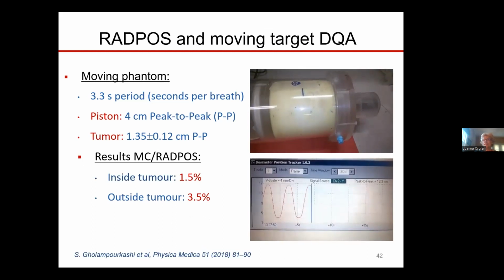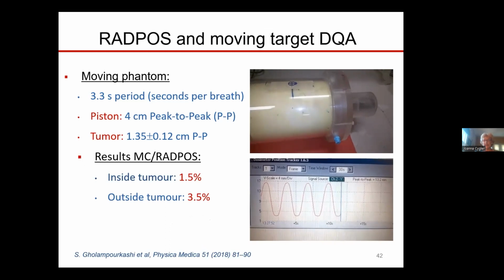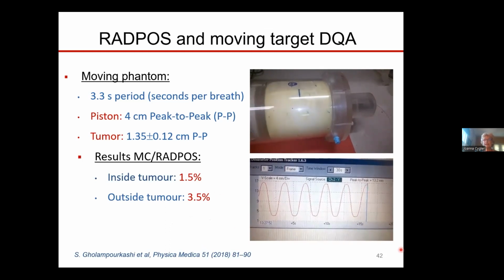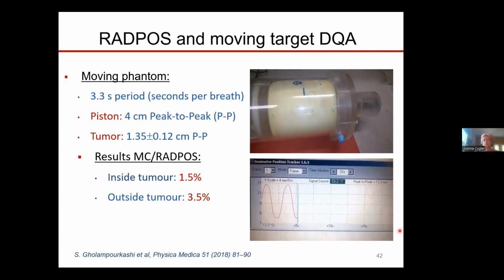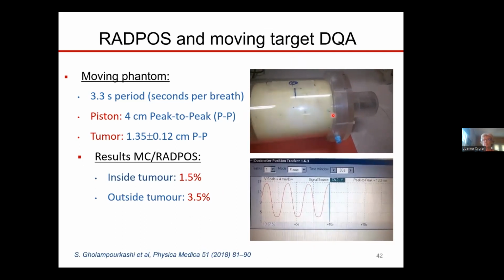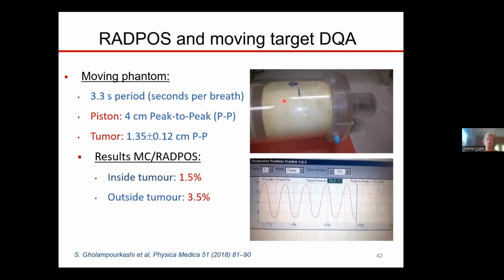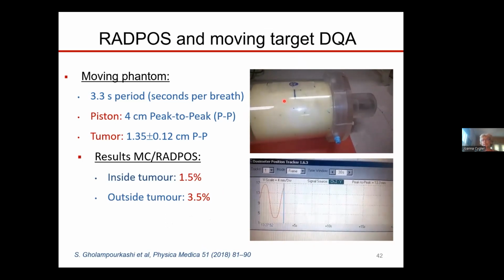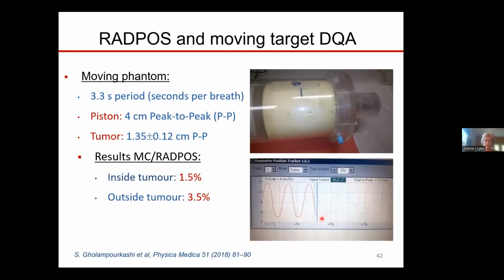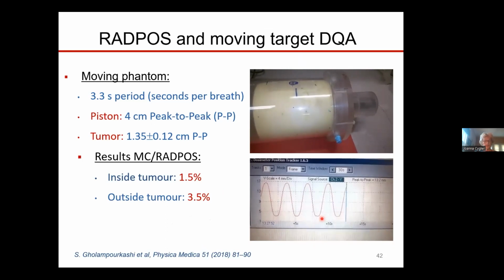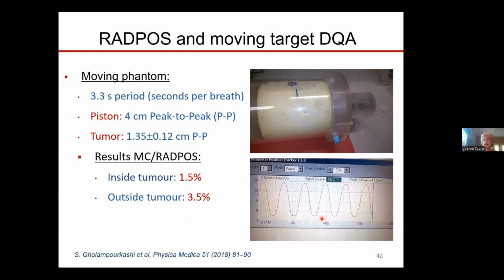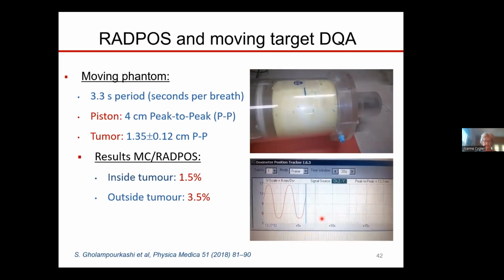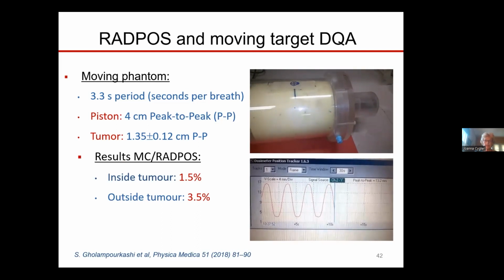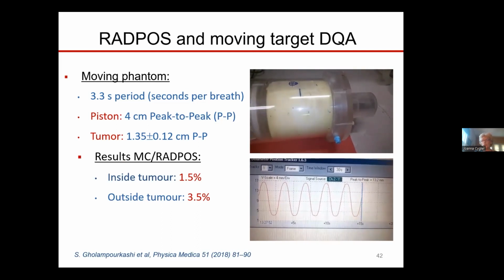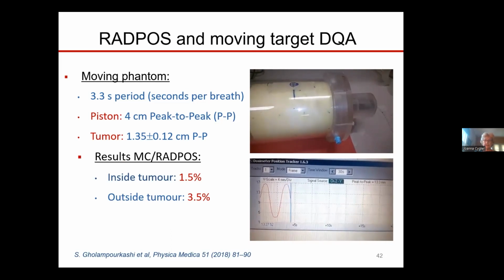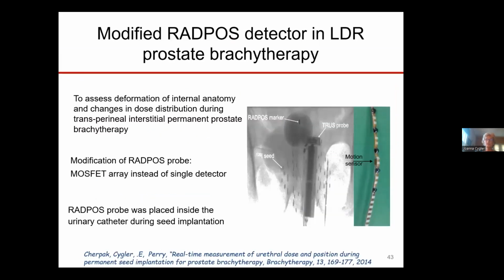This slide illustrates how the RADPOS can do these real-time position measurements. Here is the interface that we use to do those measurements. We developed a special deformable phantom, and inside the phantom is a tumor, and the RADPOS detector can be put inside the tumor or outside the tumor in various locations. And we receive the information in 3 dimensions instantaneously or as a composite displacement. We use this detector in phantom or in patients in external beam, but also in brachytherapy. And on the next slide, I will show you some of those measurements.